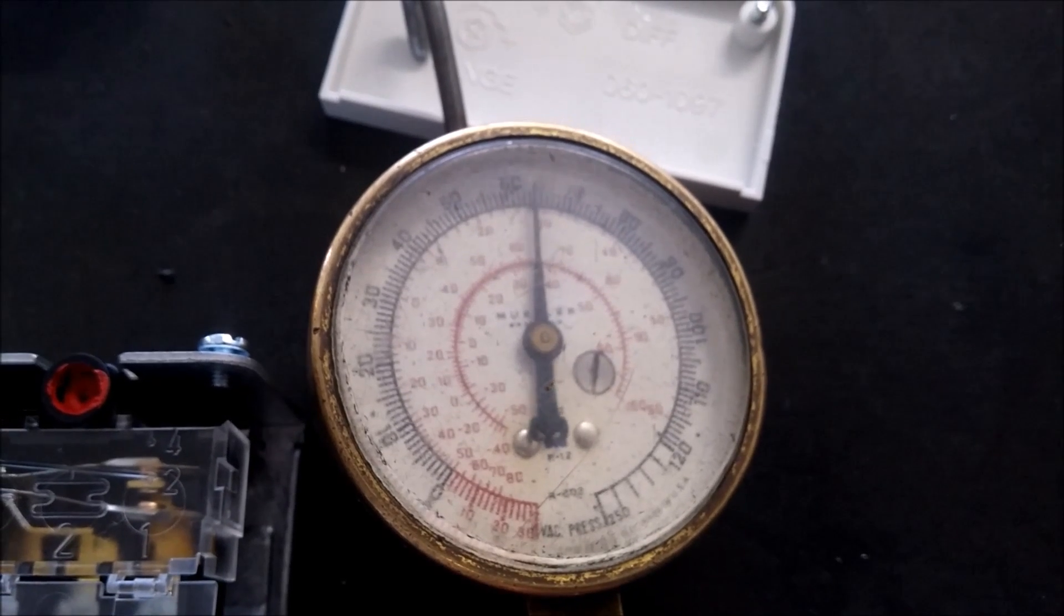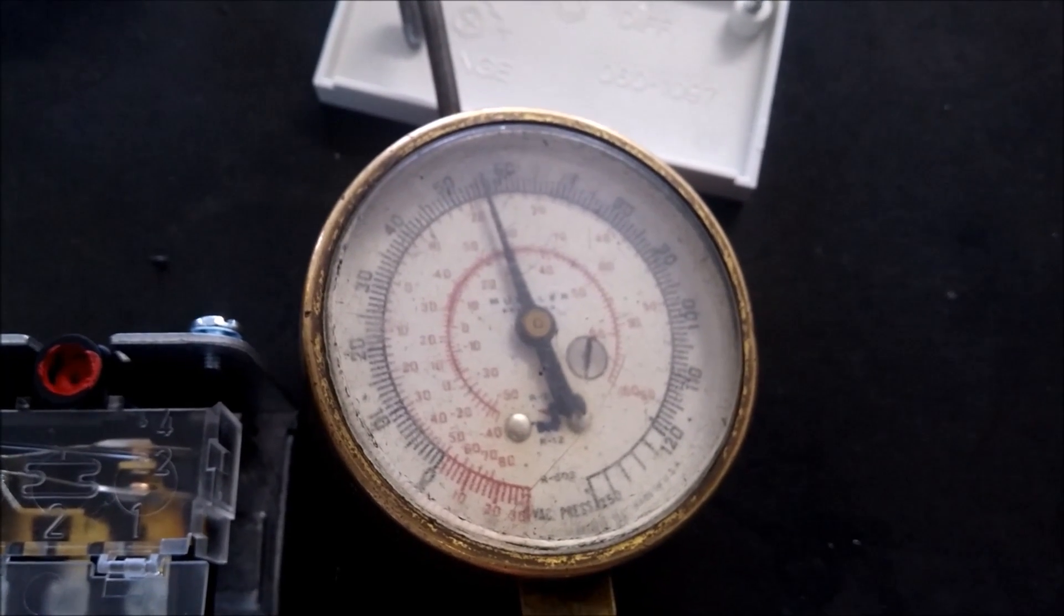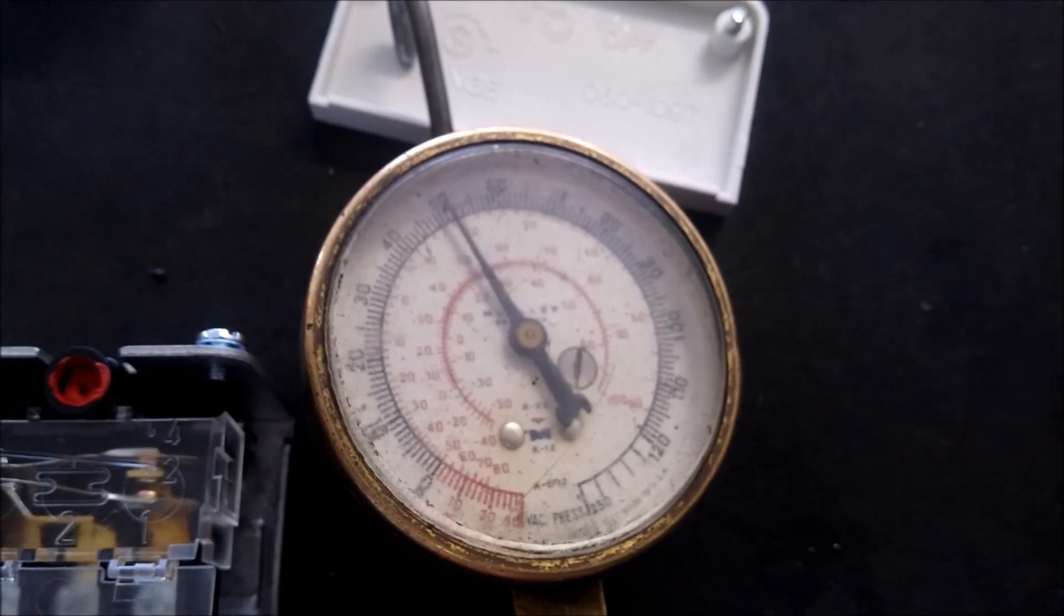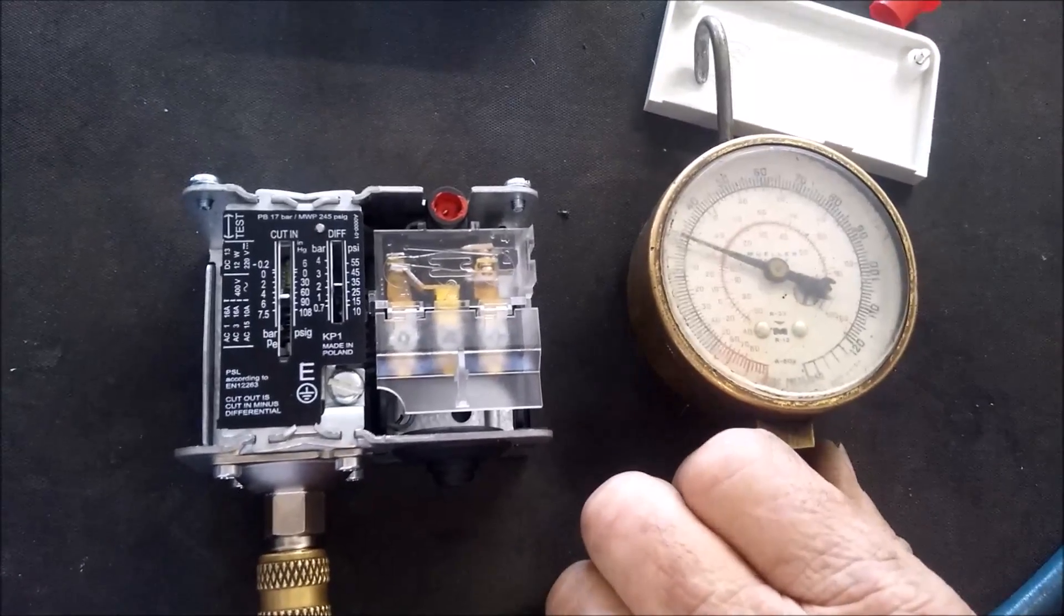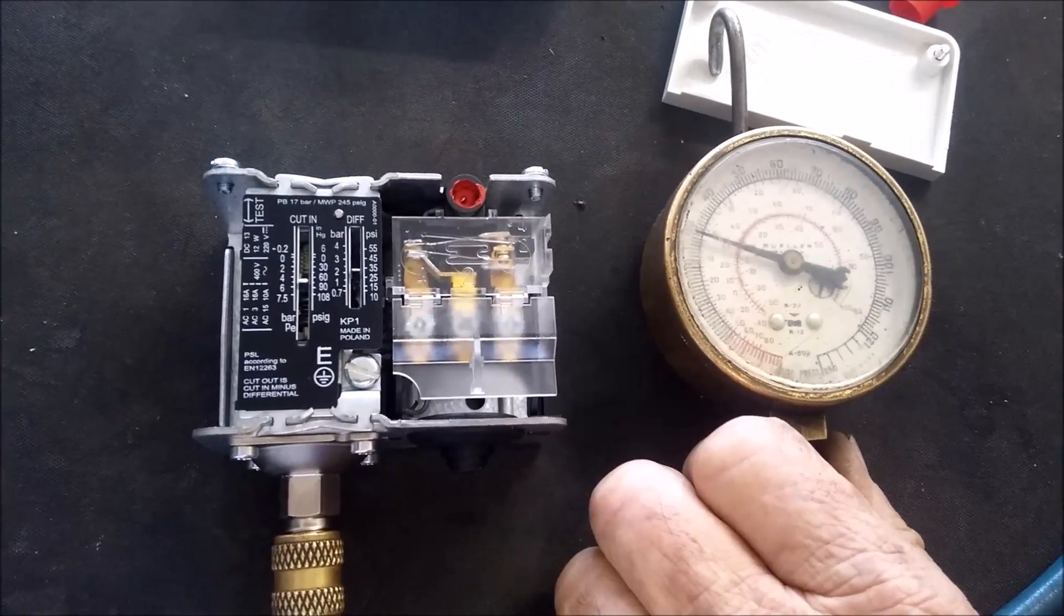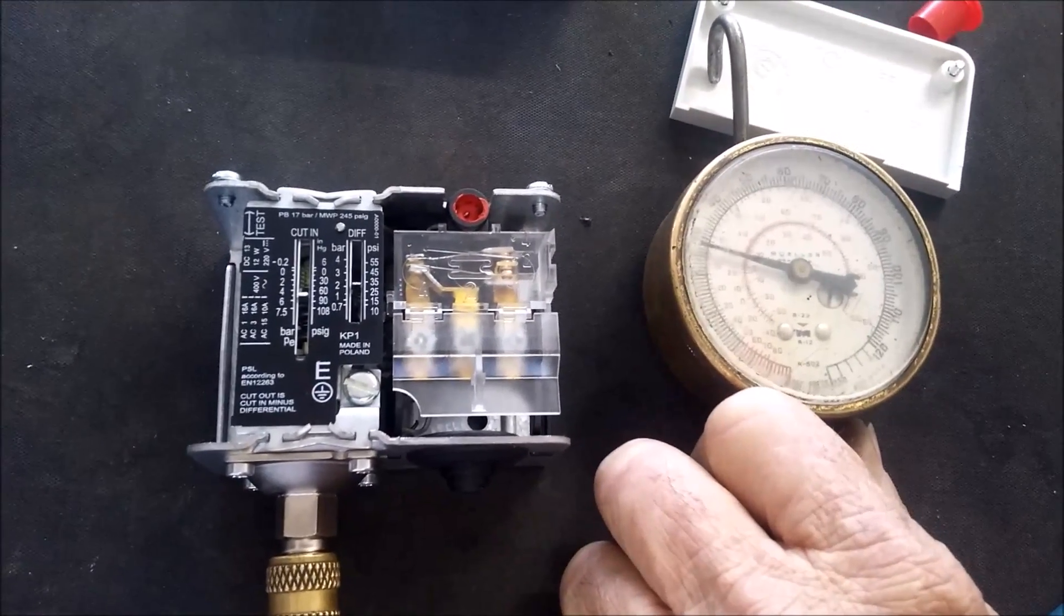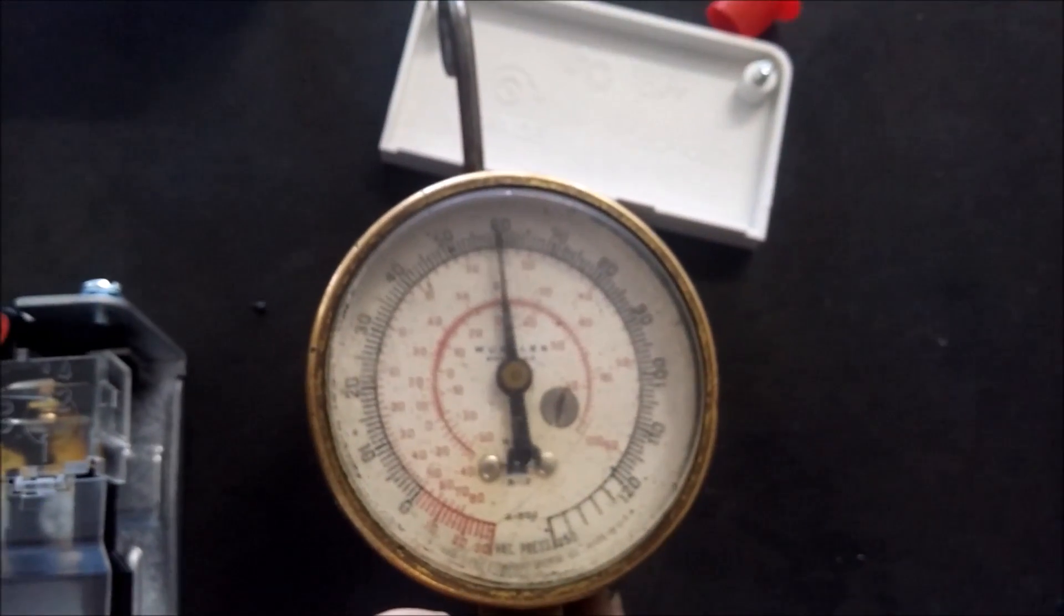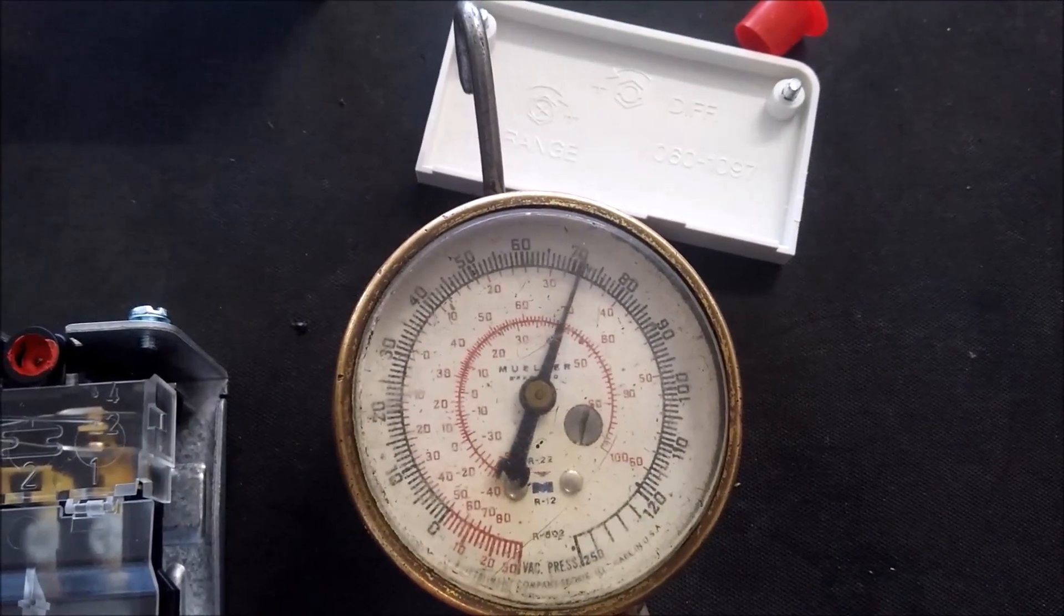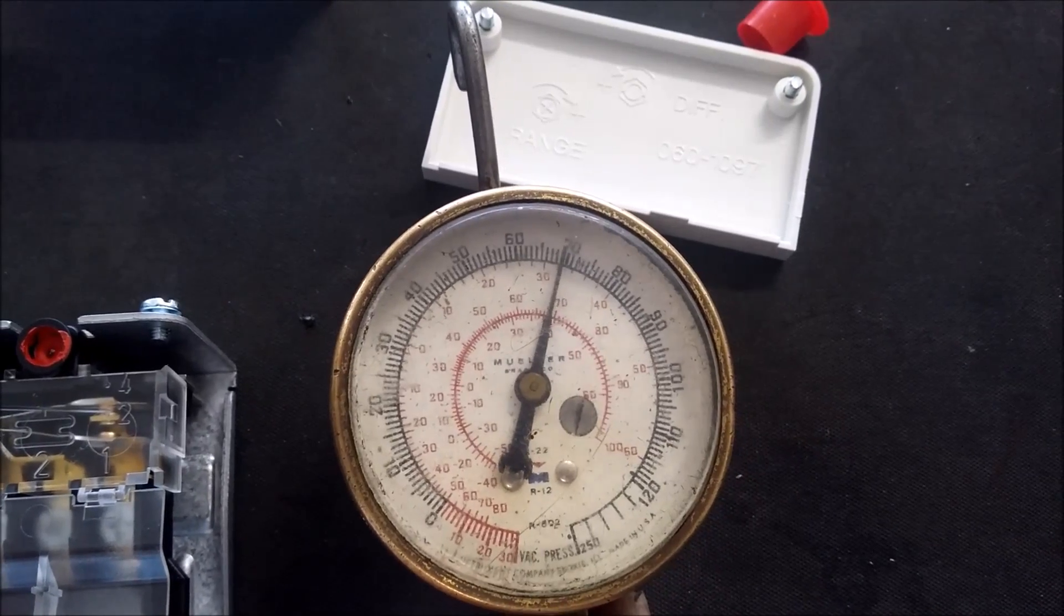70 stays the same. Now, I think I've got it for R22, I've got it almost right. So now the fridge is off and the pressure rises, and we want to go above 70 PSI. There's just over 70 PSI, the motor switched off - I mean, switched on.